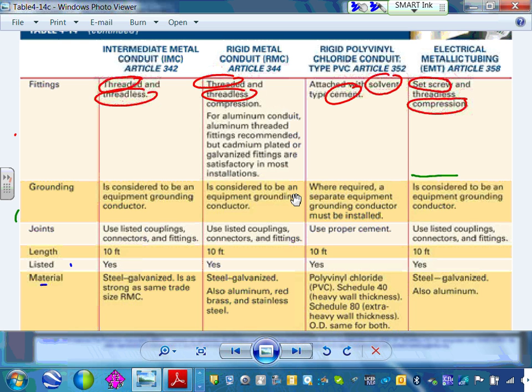Now with rigid, this is something a lot of people don't understand. With rigid and intermediate, you can have two types of connectors. You can have a connector that's threaded like this, or a connector that actually slides into it with a set screw or compression. A lot of people think rigid is always threaded - it doesn't have to be. It's typically used as threaded because it's threaded, so you use threaded connectors with it, but you can use non-threaded.